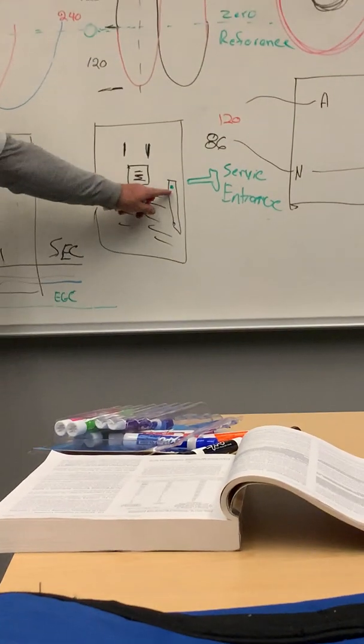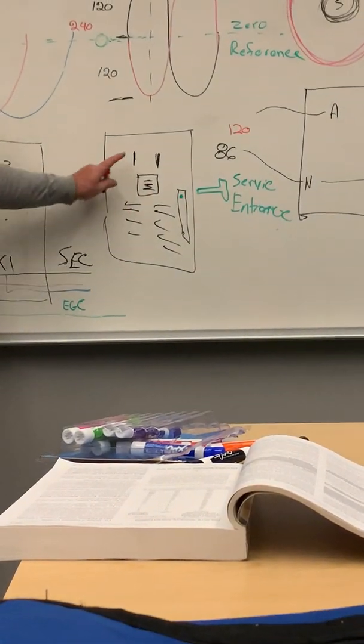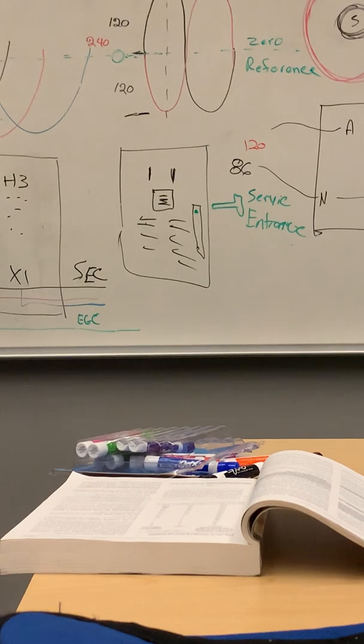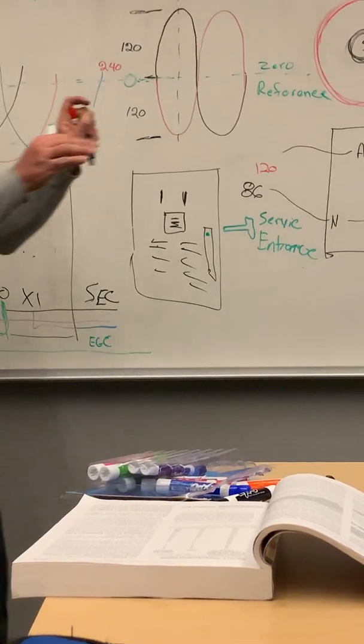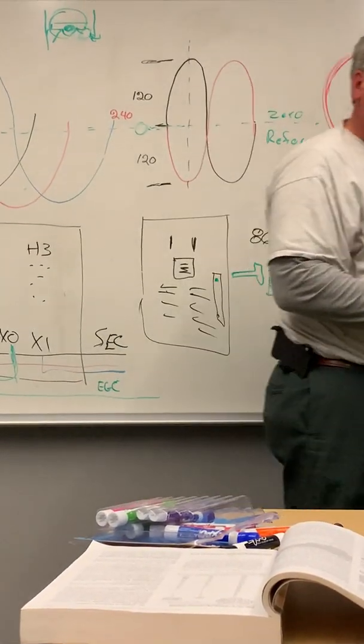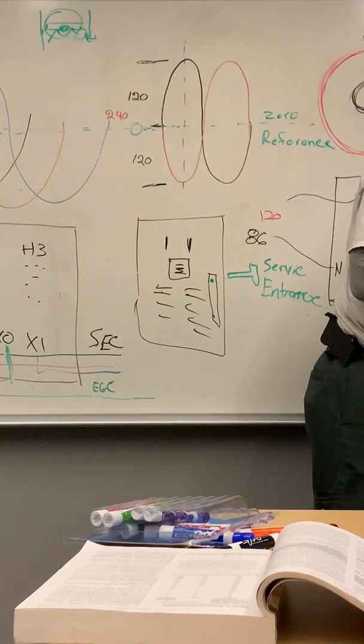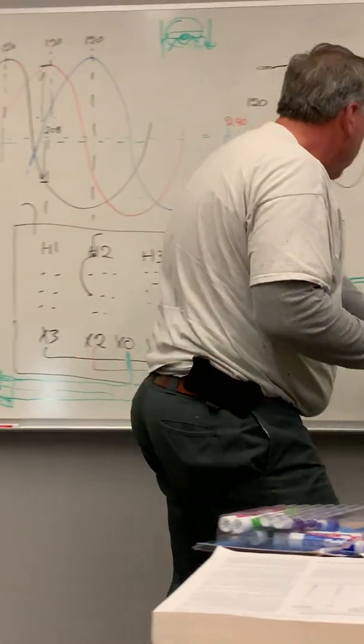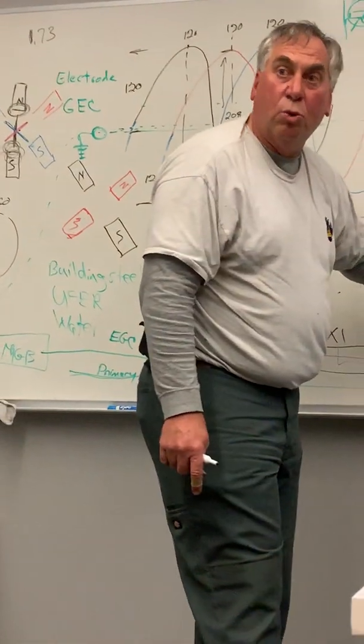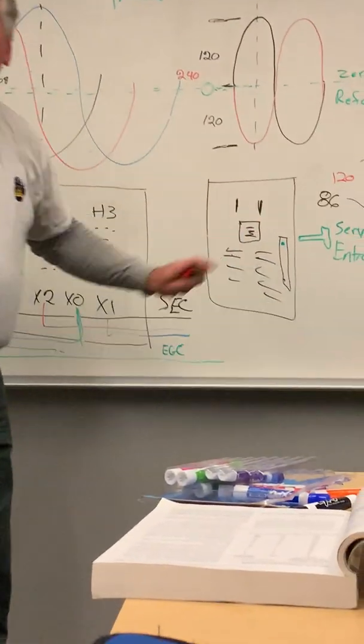The rest of the time, you would not bond the neutral to the ground; you keep it separate. So when you keep it separate on the next sub-panels down the line, it gives that low impedance path all the way back to where you want it to meet, so that it will trip the breaker.